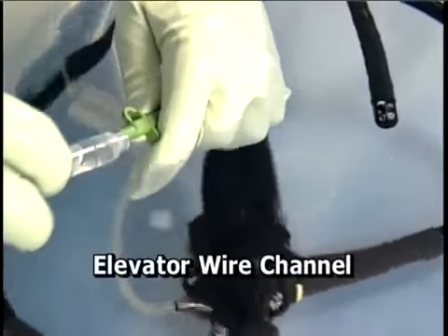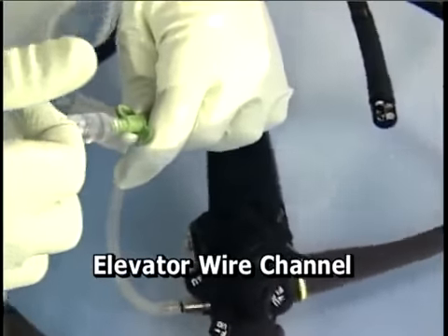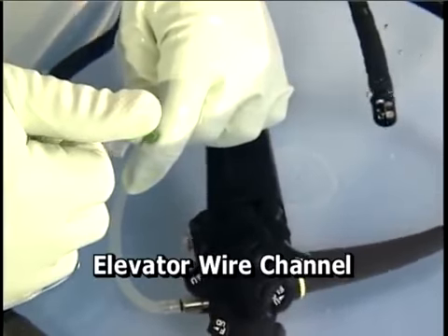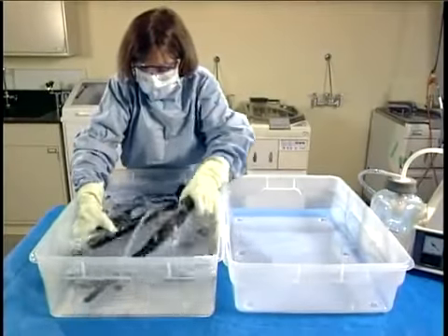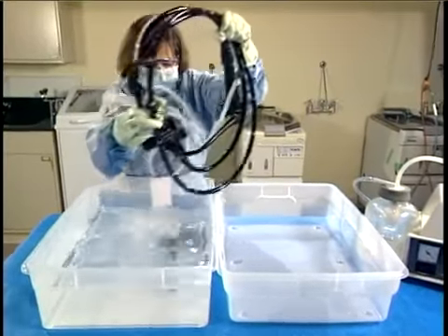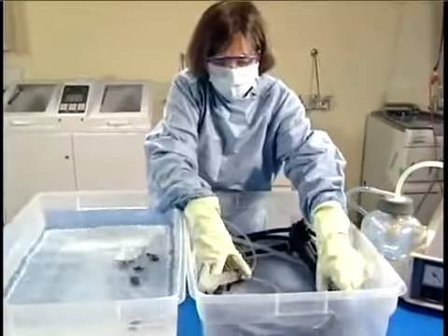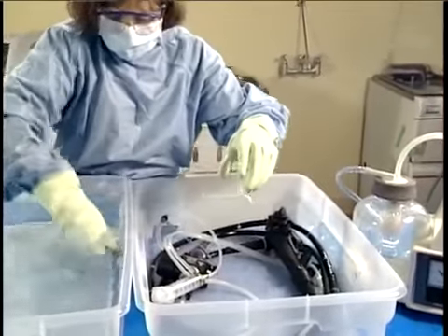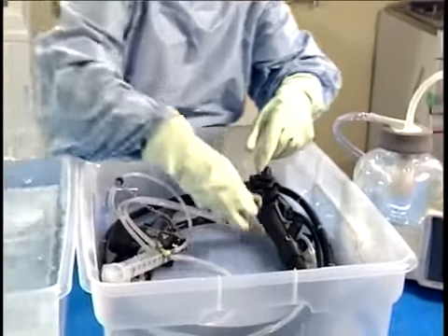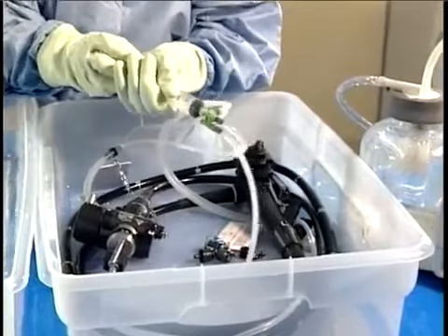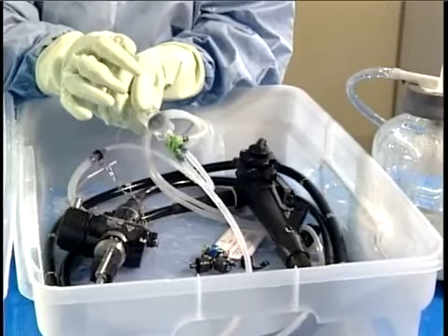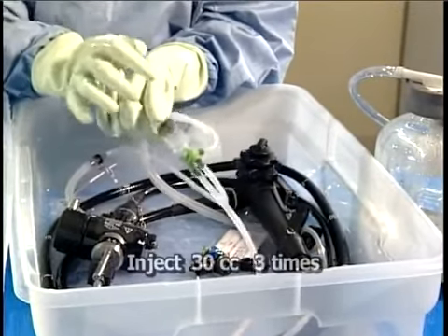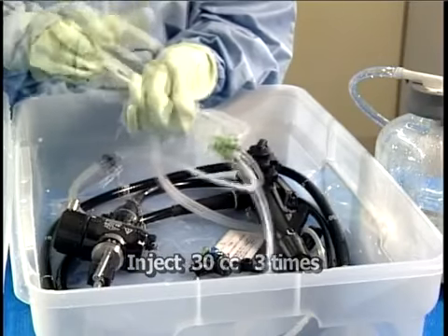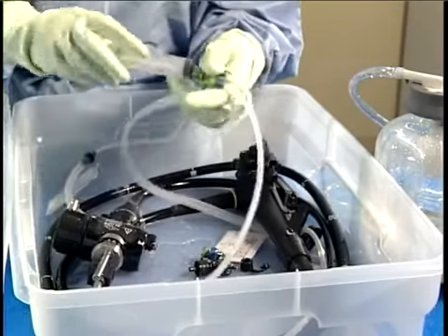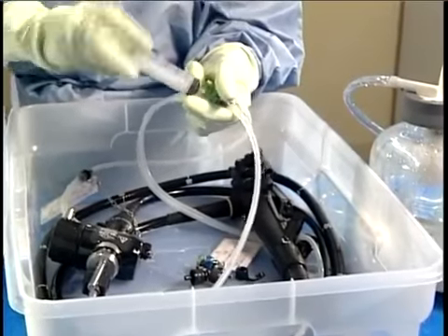If you are reprocessing a duodenoscope, inject water into the elevator wire channel in order to rinse this channel as well. Remove the endoscope and accessories from the rinse water basin and place them into a clean, dry basin. Use the syringe once again to flush all water out of the suction channel. Move the syringe and flush out the air-water channels.